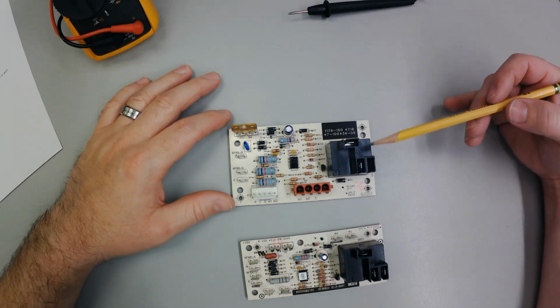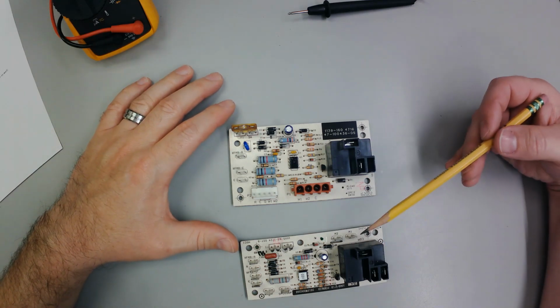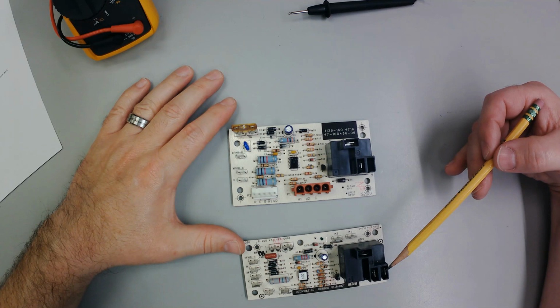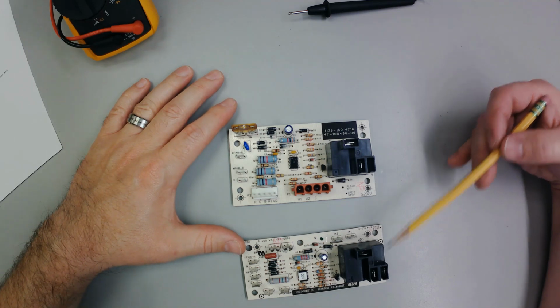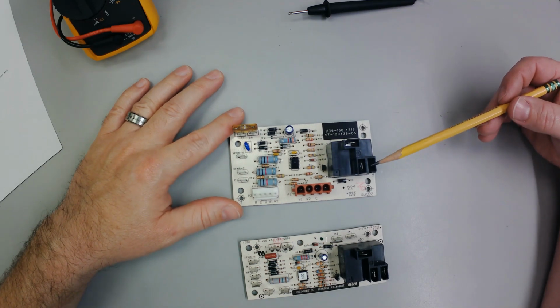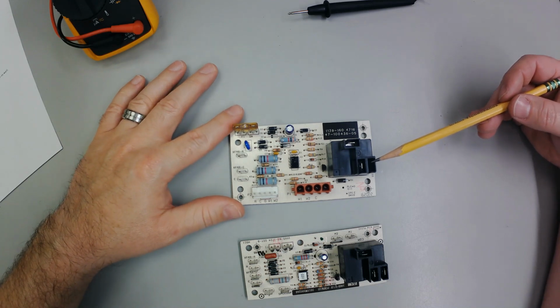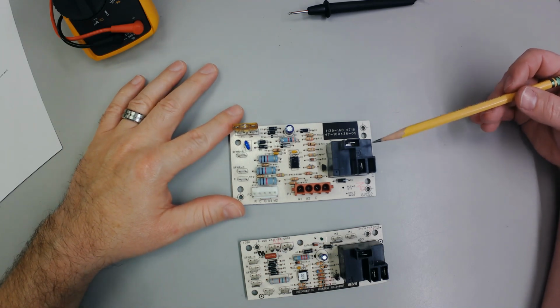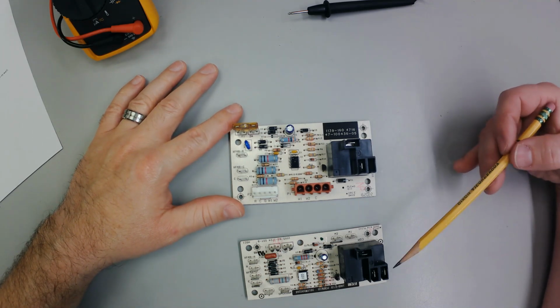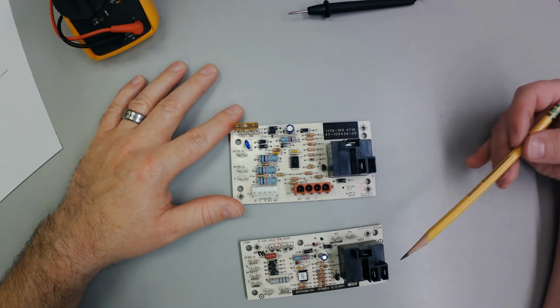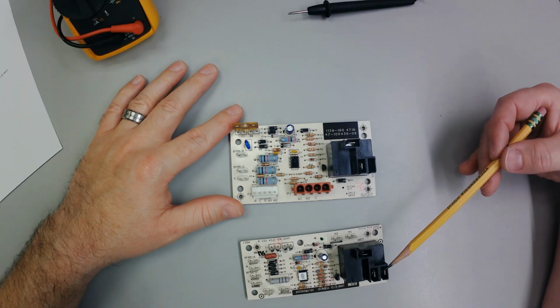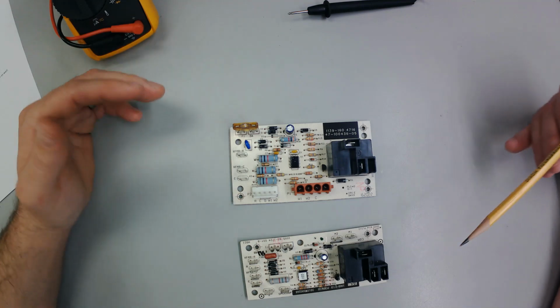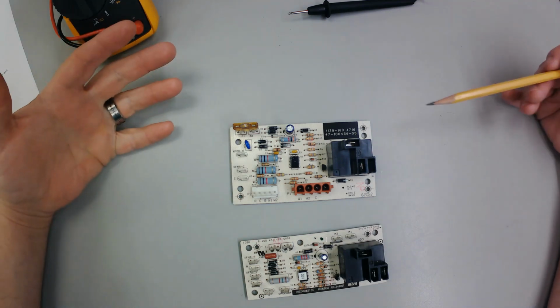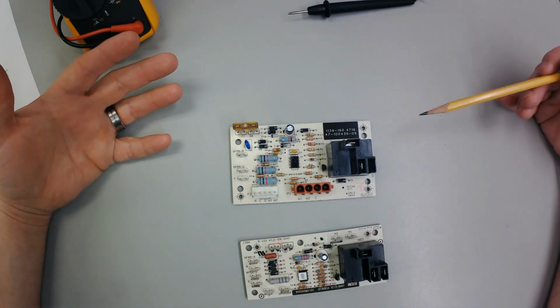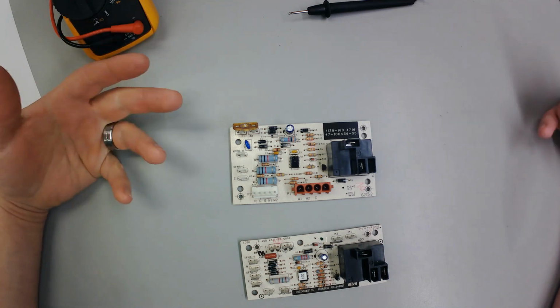So on this air handler, where Goodman has a purple wire coming through to the normally closed from off of the heater circuit, I don't have that with this Rheem. It's more simplified. It's very easy to understand as far as the heater wiring, but the fan is where people are missing, because this normally closed safety or normally closed switch is like a redundant safety. I can piggyback off of the high voltage heater circuit and get the fan to come on regardless.